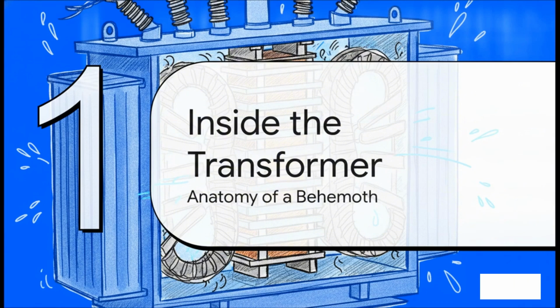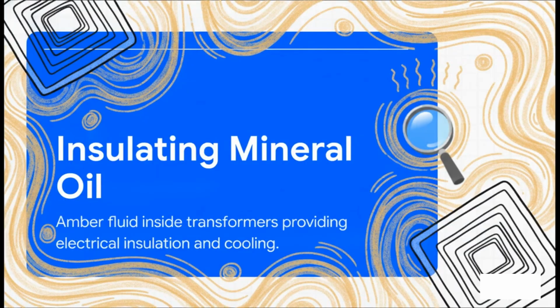So let's look inside the power transformer and explore the anatomy of a behemoth. If you could actually peek inside one of these, you'd find the magnetic core and this complex web of high and low voltage windings where the heavy lifting of voltage conversion actually happens. Surrounding that core is a very specific type of liquid, insulating mineral oil. It's a highly refined amber-colored fluid used inside transformers to provide crucial electrical insulation, and most importantly for our story today, cooling. At rest, under a light electrical load at around 25 degrees Celsius, this fluid is perfectly calm. It naturally fills the main tank, completely submerging those inner workings to protect them.